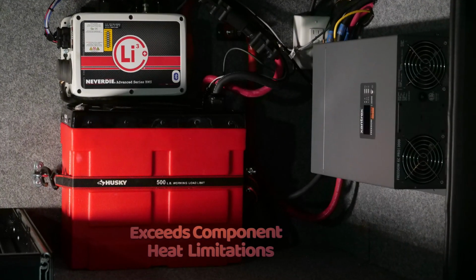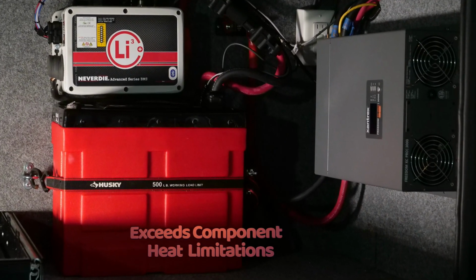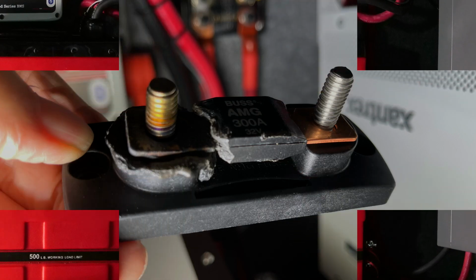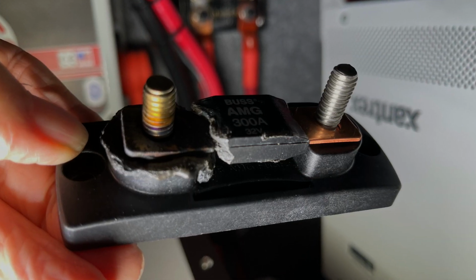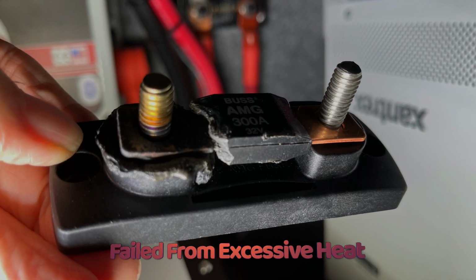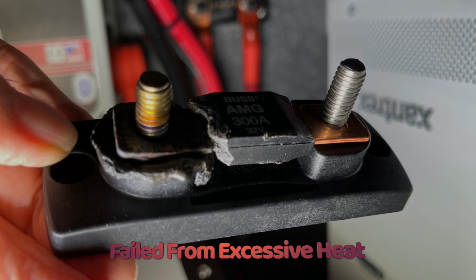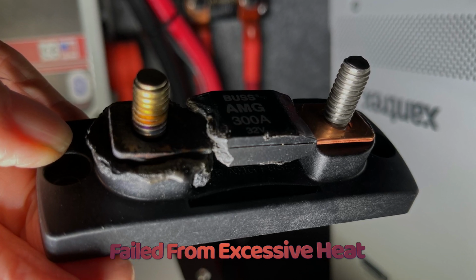This heating can exceed the component's heat limitations, then fail. As an example, during summer use, this owner's Blue Sea fuse holder, which was torqued to specs, failed running only 1 air conditioner, operating well below the rated fuse level.